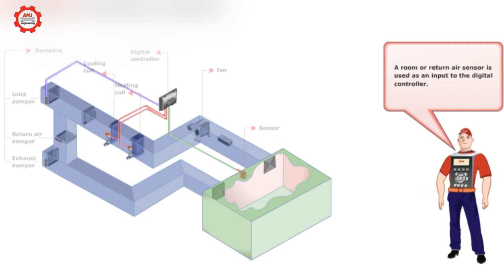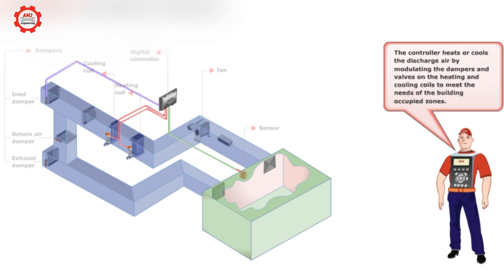A room or return air sensor is used as an input to the digital controller. The controller heats or cools the discharge air by modulating the dampers and valves on the heating and cooling coils to meet the needs of the building occupied zones.